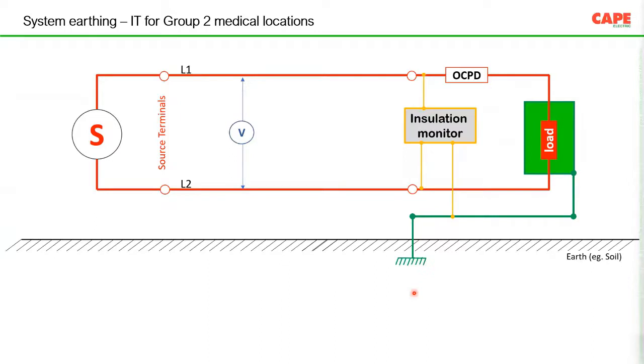Similarly, for group 2 medical locations, we can also go for IT, meaning insulated, isolated supply, with insulation monitoring devices and a leakage current monitoring system. For example, an IT system means you have the source, probably an isolation transformer, and on the secondary side of the isolation transformer, line 1 and line 2 with a voltage of, let us say, 230 volt. These two lines are completely insulated, so they are never connected to earth. Now you have an insulation monitoring device, and this entire system is sometimes called a hospital IT panel. A hospital IT panel for group 2 medical locations is one of several requirements.